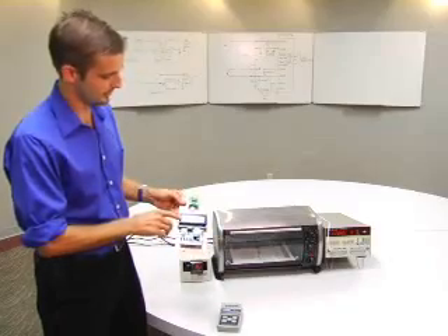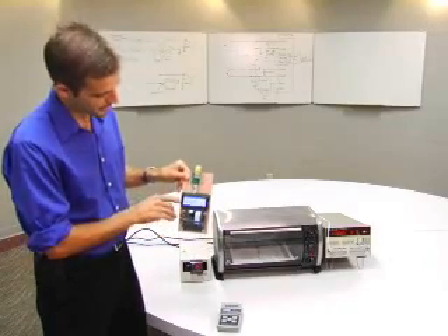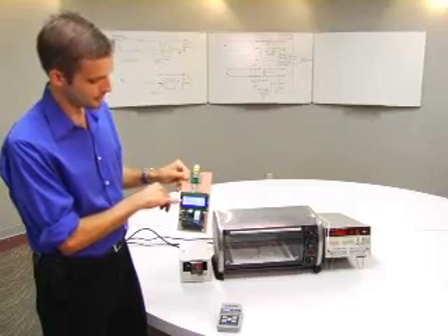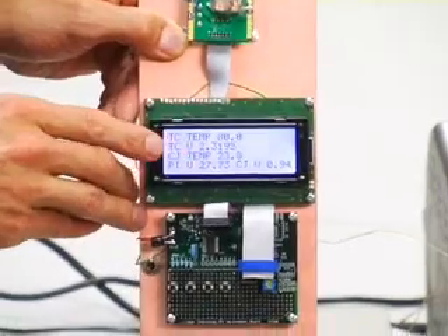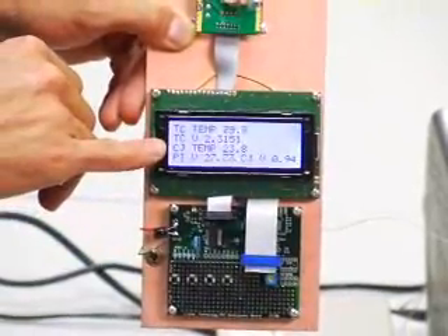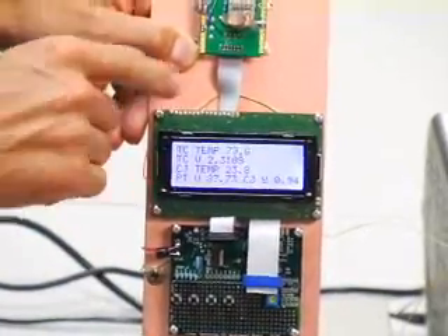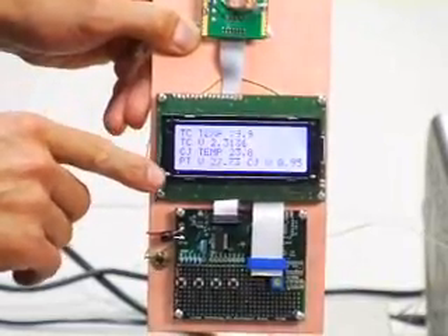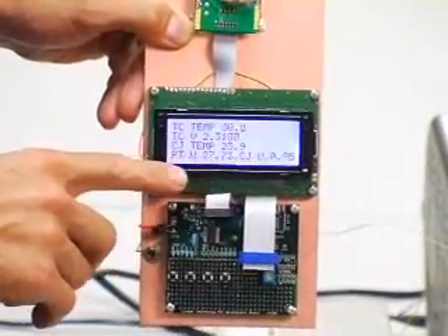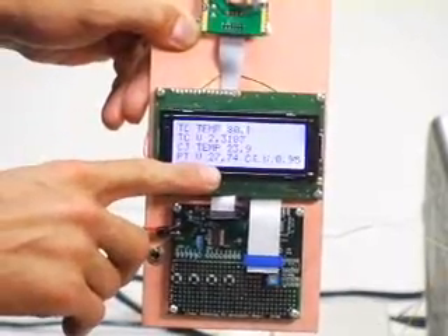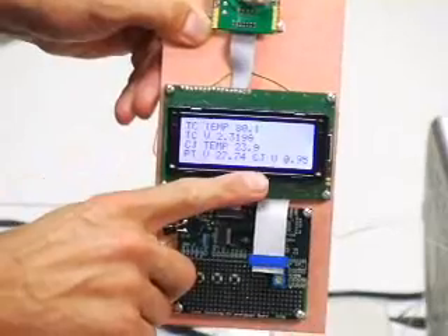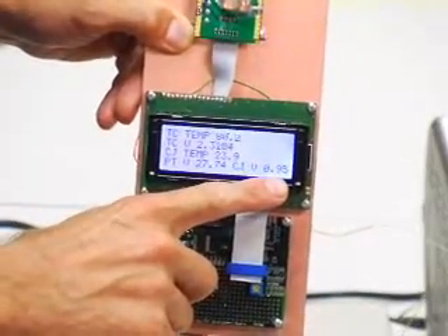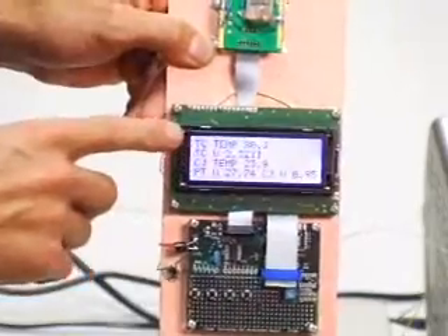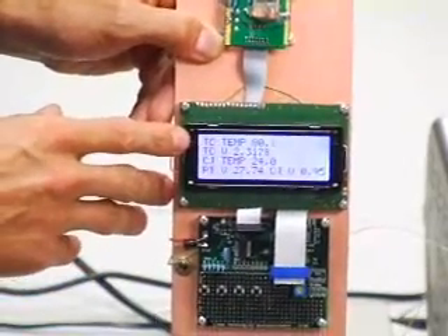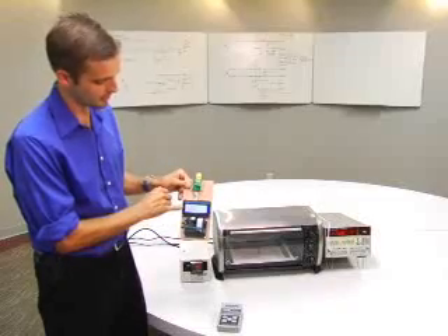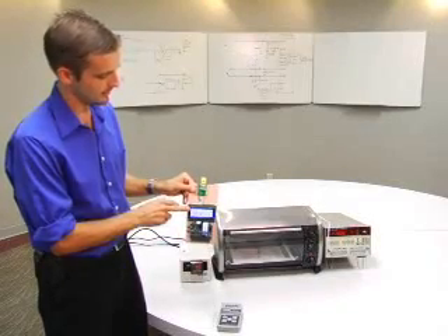Some other information, and this will help with understanding how these meters work a little bit better. We've also got the thermocouple voltage, which at 80 degrees centigrade is about 2.3 millivolts. The cold junction temperature is about 23.8 degrees centigrade, which is the temperature of the internal temperature sensor. The PTAT voltage, or the voltage output from the temperature sensor inside the A to D converter, is about 27 millivolts. And the calculated cold junction voltage is about 0.95 millivolts. And as we saw before, the cold junction voltage at room temperature is about a millivolt. So this voltage is subtracted from the thermocouple voltage, and temperature is calculated from that.